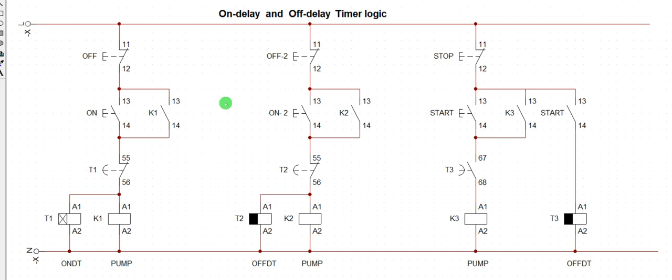I repeat again, there is a function called cooldown duration. Cooldown duration is a particular function we use to shut down a generator set. So if I put on a generator set and I want it to shut down after an hour, what I will do is put up a logic so that when I put on the genset, I also command it to shut down, but the genset will not shut down until after 1 hour. For that logic, I will use an off delay timer to shut down the gen after 1 hour. And after that 1 hour, when the gen shuts down, the entire circuit is closed. The signal for the circuit is shut off.